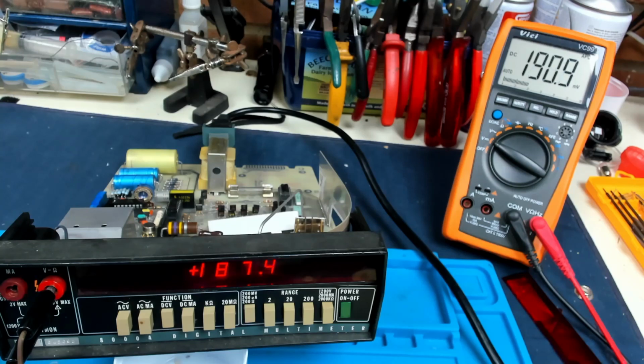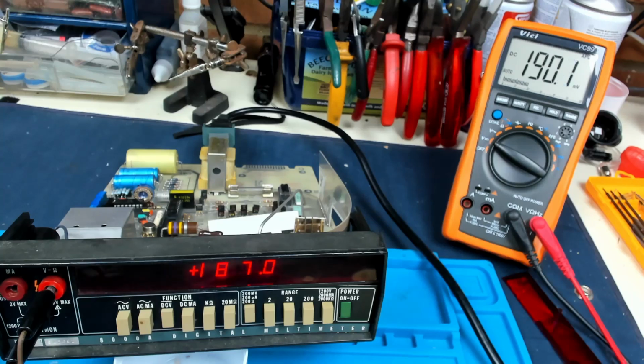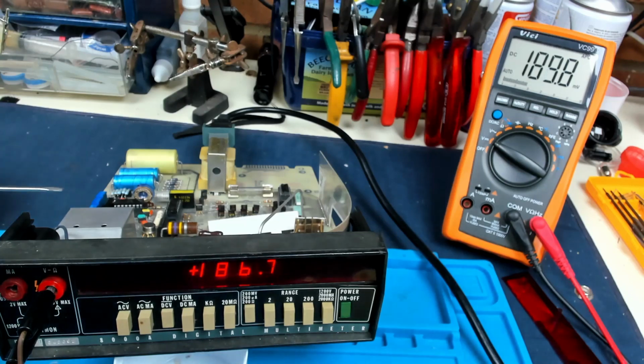I'm still trying to get it to adjust. So there we are, it's about 190. But if you leave it there, you'll see that it will fluctuate slightly. It's dropping down there. It's not a calibrated bench power supply in any way, shape or form. My meter's not right in that respect. But we can see there that we have got 190, but on the Fluke we've got 186.9. So I should be able to, and I can see the pot here, I should be able to hopefully just gently adjust this to give us 190 on the meter. I'm just creeping it up slightly. 187. We're going down. 188, 189. I'll keep turning it. 189.